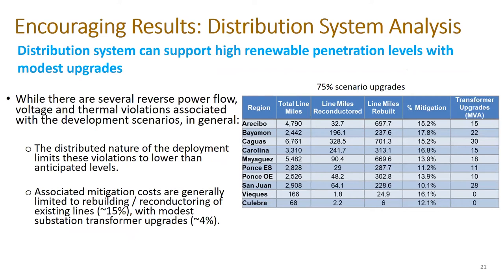Now, what did we find out? We were actually pleasantly surprised. When I went into this, I was anticipating that as a bare minimum to reach a 75% scenario, we were probably going to have to improve at least 30, if not 40, or even perhaps more percent of the overall distribution infrastructure. That was based on previous experience where we were installing relatively large penetrations, but at lumped locations. By distributing the DER in the fashion that we did, the amount of infrastructure repair, mitigation, however you want to characterize it, was substantially lower than I initially expected.